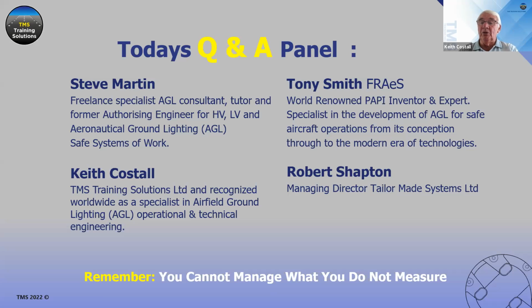When it's a screened cable, we earth down that screening to help protect from that situation. But in the US, for example, they use unscreened cable, so they are potentially more prone to that crossfeed. So you could have a power unit switched off for its circuit, yet some lights in that circuit have power on them because of crossfeed, induced EMF from an adjacent circuit. This does happen.